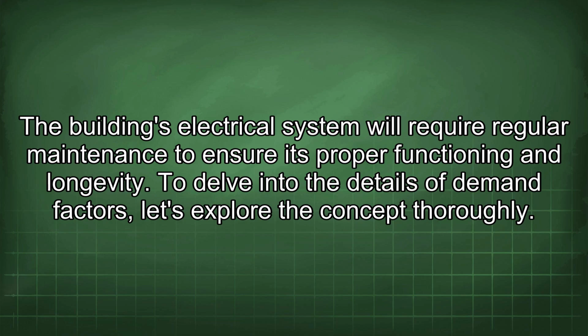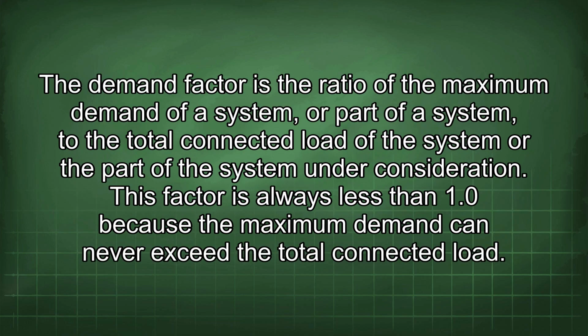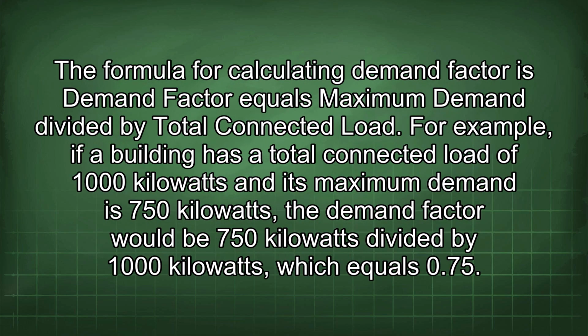To delve into the details of demand factors, let's explore the concept thoroughly. The demand factor is the ratio of the maximum demand of a system, or part of a system, to the total connected load of the system or the part of the system under consideration. This factor is always less than 1.0 because the maximum demand can never exceed the total connected load. The formula for calculating demand factor is demand factor equals maximum demand divided by total connected load.